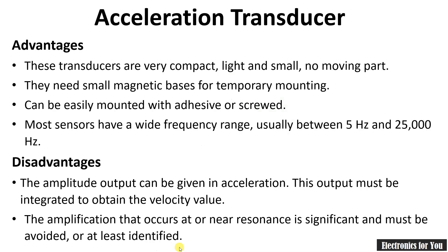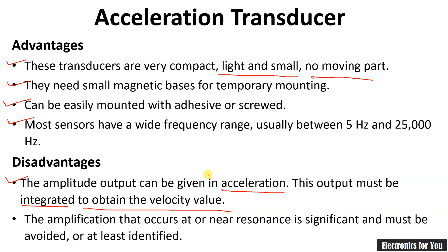Advantages of the acceleration transducer: these transducers are very compact, light, and small with no moving parts. They need only a small magnetic base for temporary mounting and can be easily mounted with adhesive or screwed in place. Most sensors have a wide frequency range, usually between 5 hertz and 25 kilohertz. Disadvantages: the amplitude voltage output is given in acceleration units, which must be integrated to obtain the velocity value. The amplification that occurs at or near resonance is significant and must be avoided or at least identified.